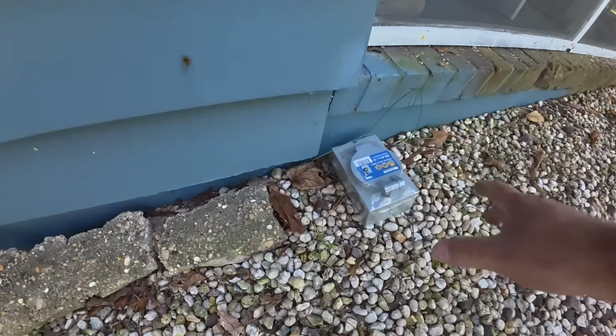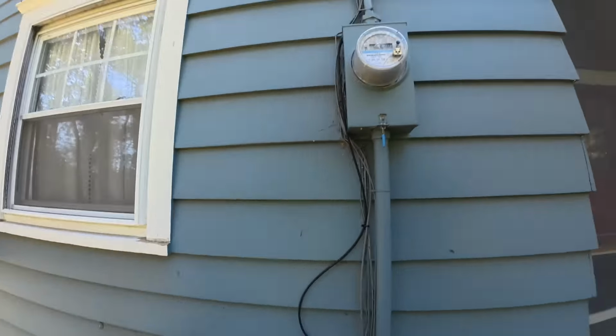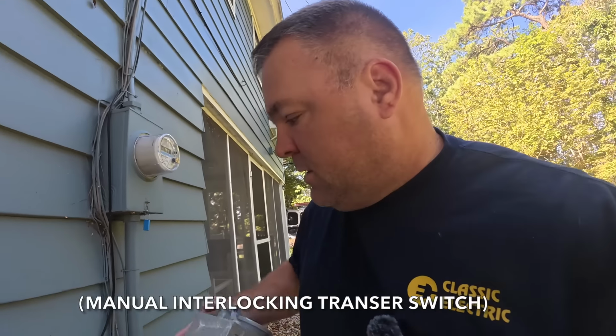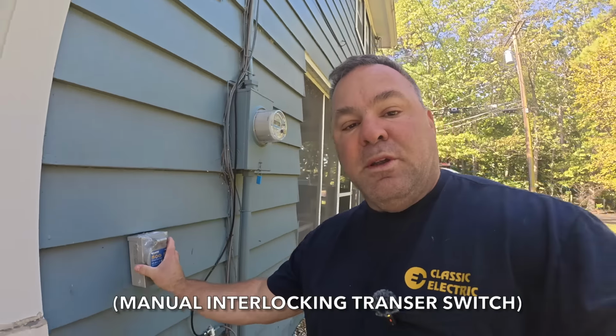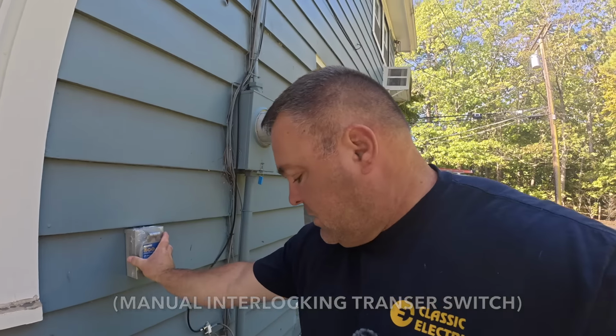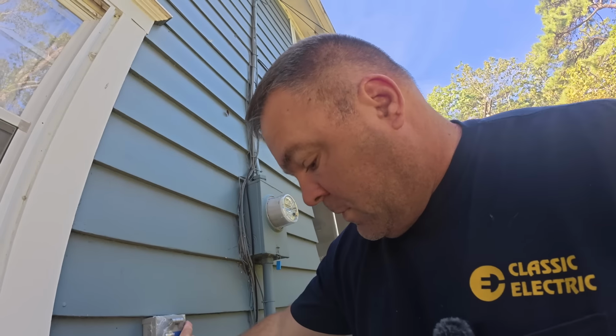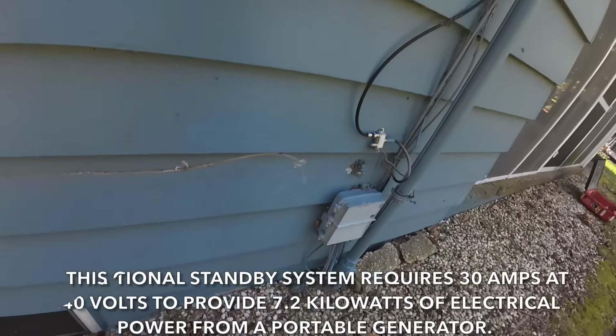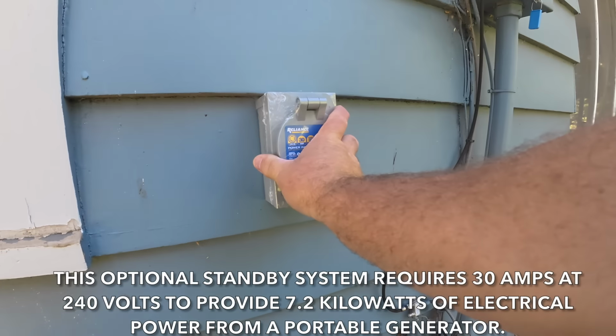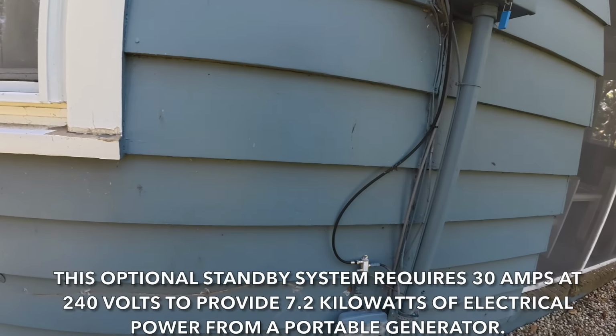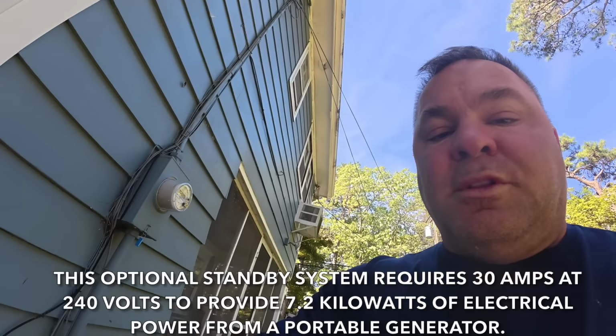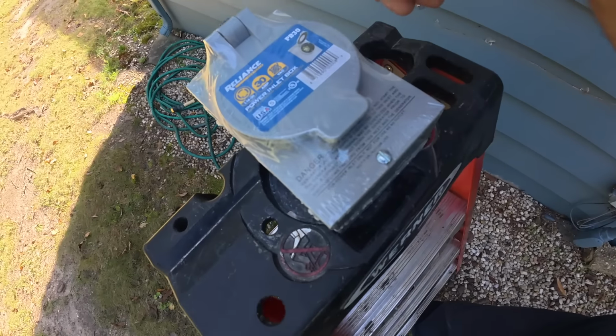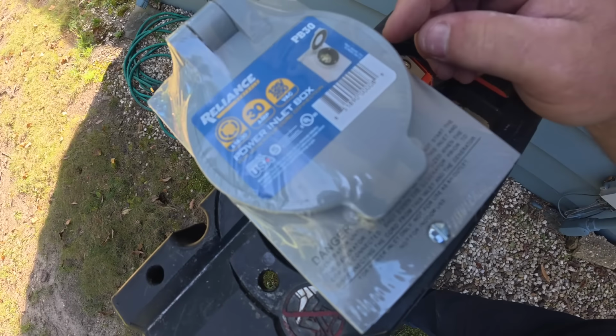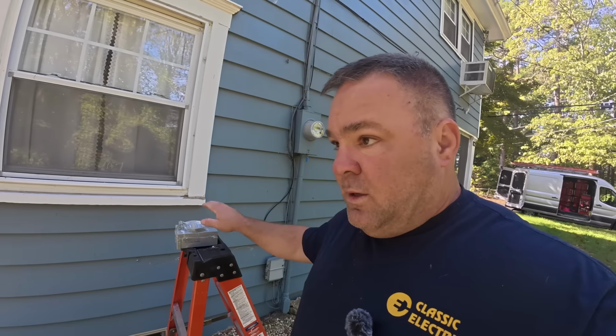Part of this job also, we're going to be installing a manual interlocking transfer switch. This is going to sit right beside the new meter main on the house. We'll probably come through the rim joist down here with a piece of conduit into the bottom of the inlet box. It's called an inlet because instead of having the outlet, you'll see the prongs are sticking out. So you have a female cord body going into the male inlet.